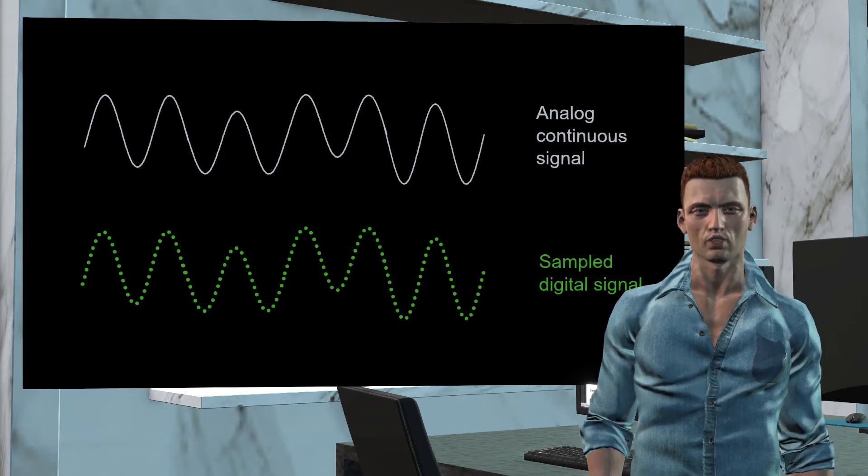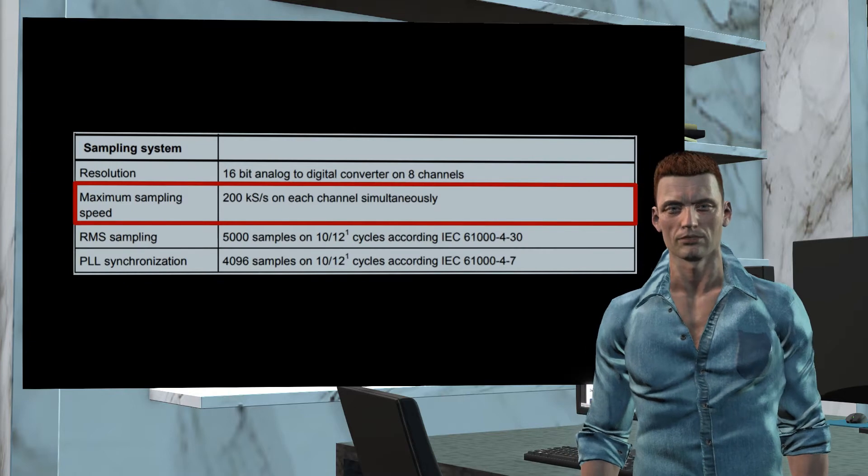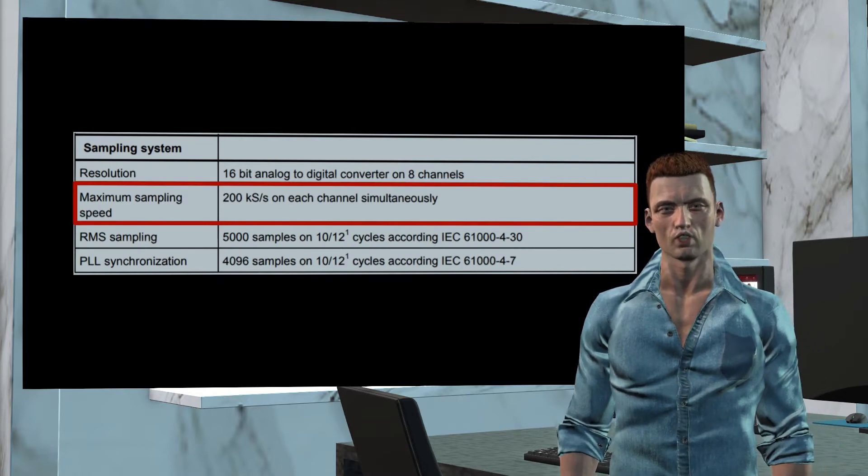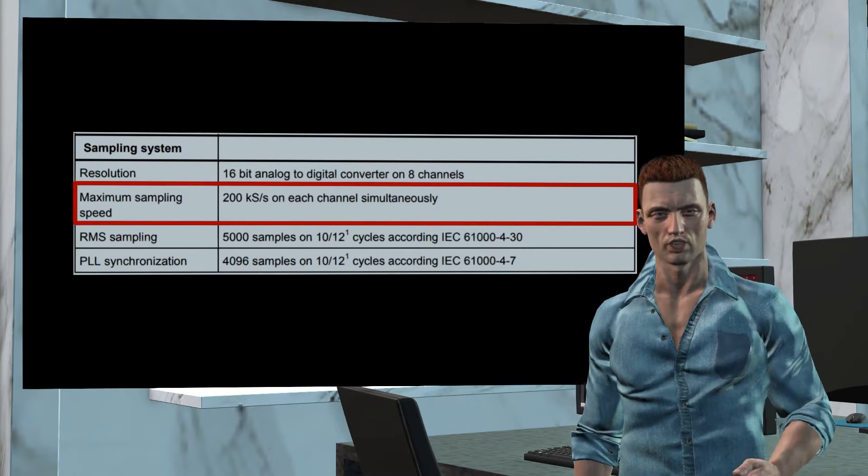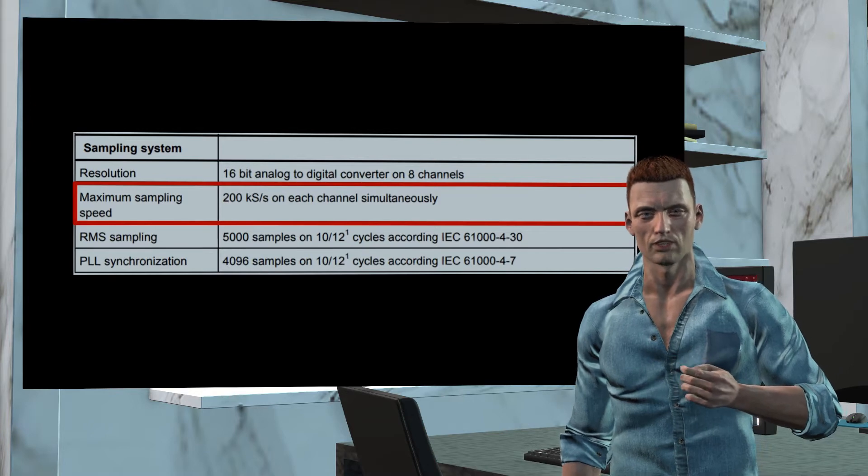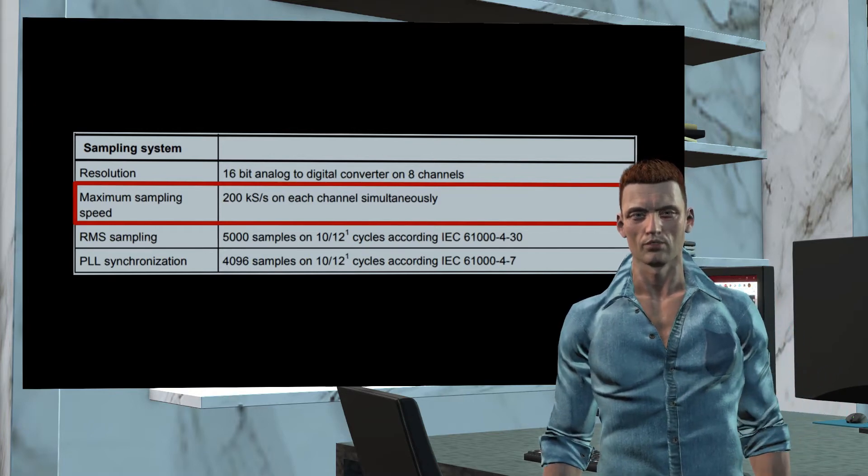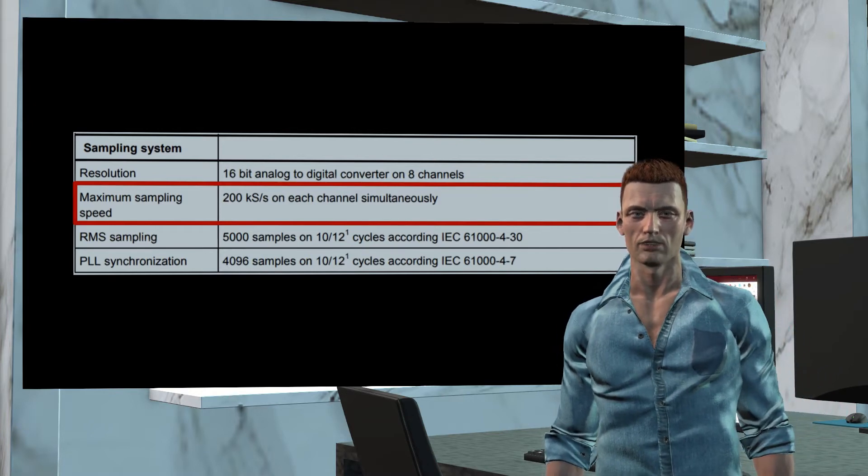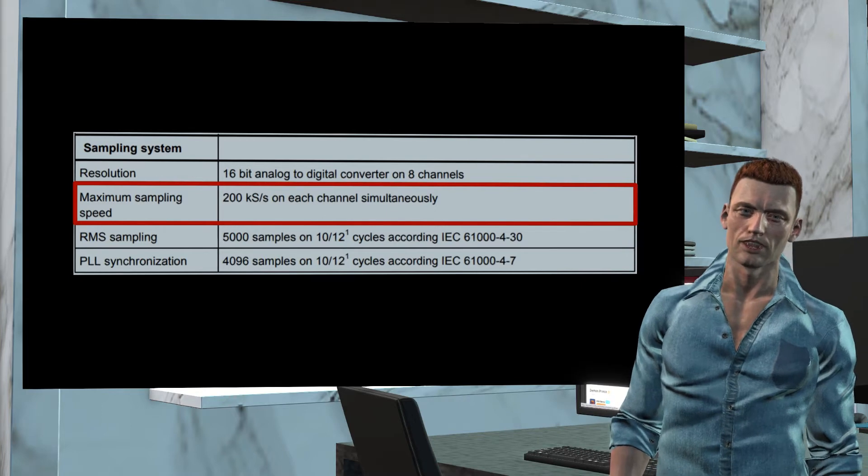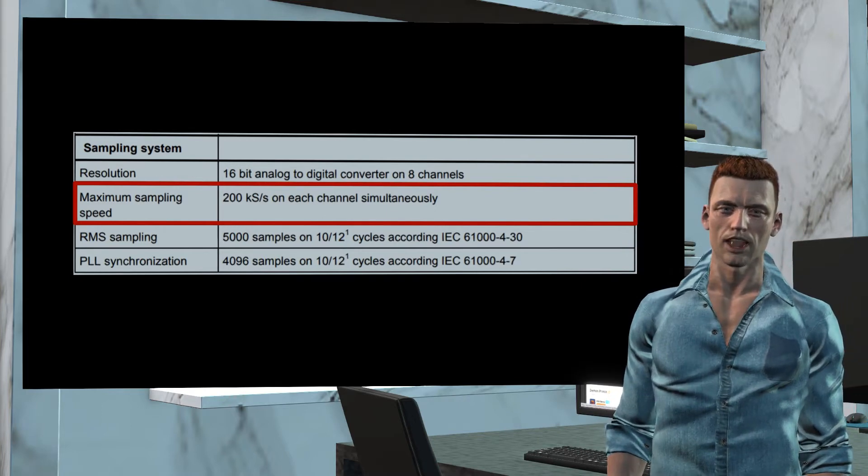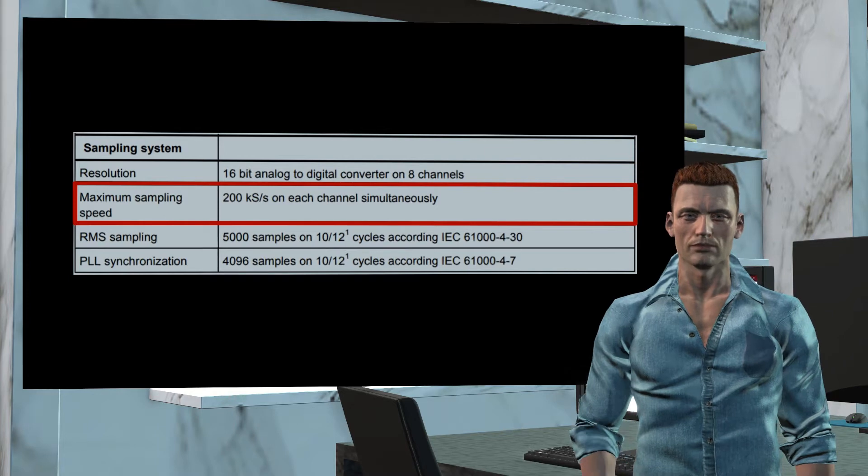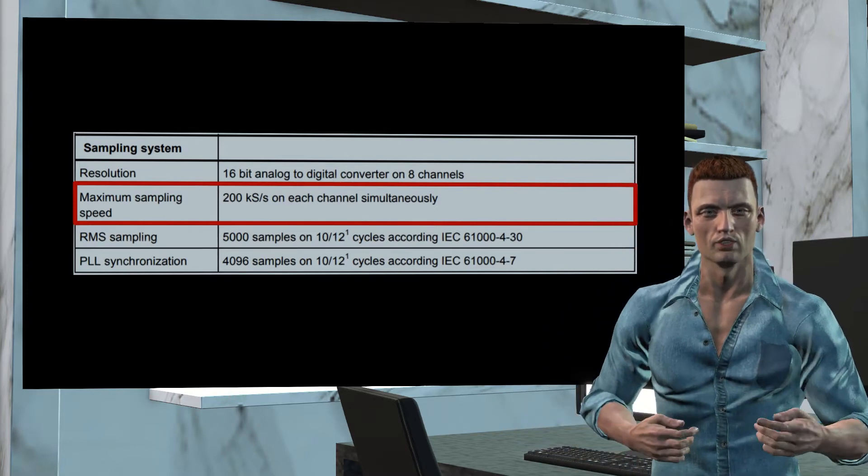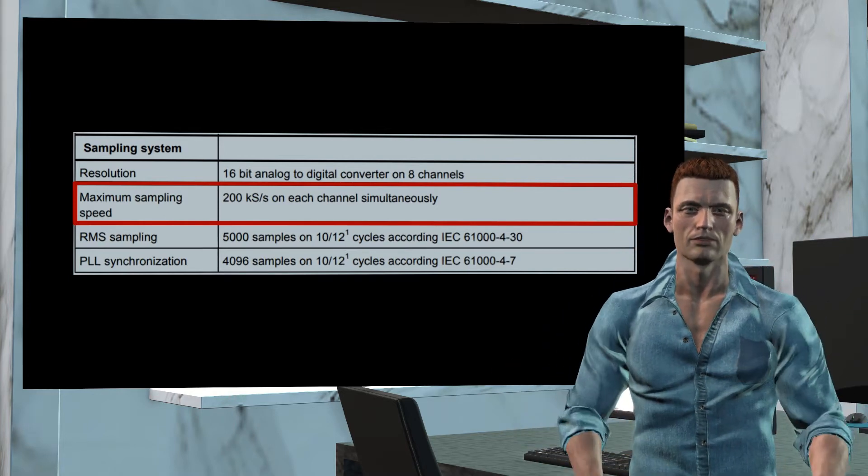In the case of the Fluke 435 Series 2, if we look at its technical specifications, we can see that the equipment uses a 16-bit analog-to-digital converter, with four channels for voltages and four channels for currents. The maximum simultaneous sampling rate for waveforms is 200,000 samples per second. This very fast speed is mainly used for event detection.